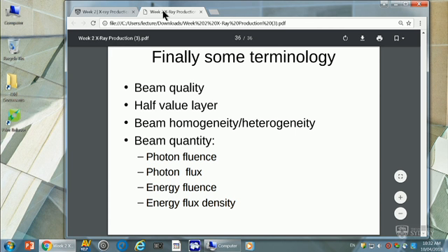Okay. The angle. The which? The angle? Yeah, the angle could have, not a major factor, but the angle could have an impact. But anode material definitely will have. Whether it's tungsten, whether it's molybdenum, how much rhenium is in there, all that will affect it. Okay, so beam quality is simply a term used. When you see quality, it simply means energy of the X-ray beam.